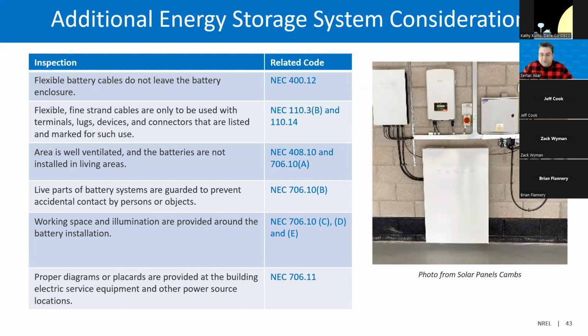Live parts of battery systems must be guarded to prevent accidental contact by person or objects. Working space and illumination must be provided around the battery installation. Proper diagrams and placards must be provided at the building, electric service equipment, and other power source locations. So these are actually basic things to check in the energy storage.